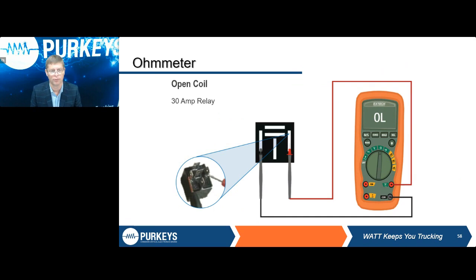We're going to check a different relay, though. We check this one, go across the coil, we get an OL. If your meter's set up properly, you're using the right scale, what that should tell you is that coil within that relay has a broken strand. I don't know if you've ever taken a relay apart, but there's a little metal core, and it's got a ton of loops of very light gauge copper wire around it. How many loops? I have no idea. I got bored trying to count them. But somewhere, we're going to say 400 loops in there. Somewhere in those 400 loops, there's one loop that's broken. So that relay cannot work because it cannot generate the magnetic field to activate.